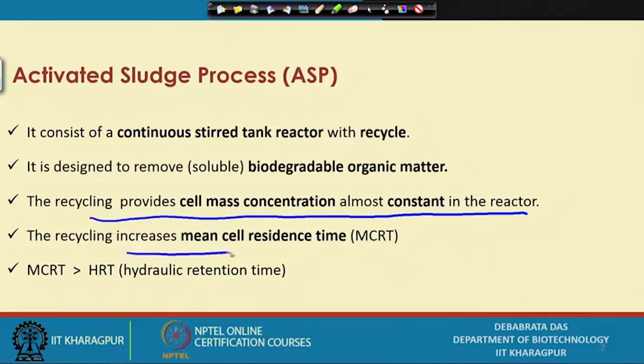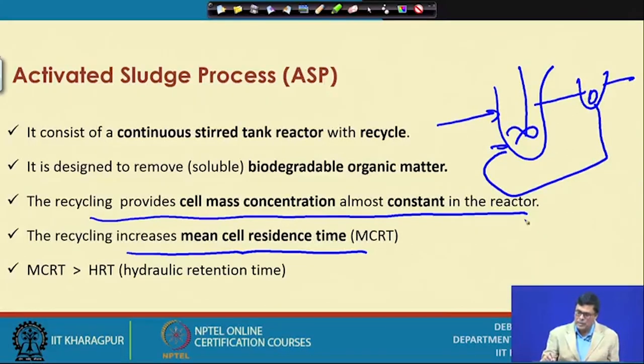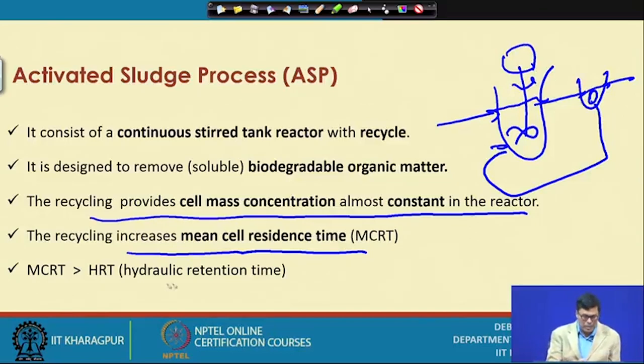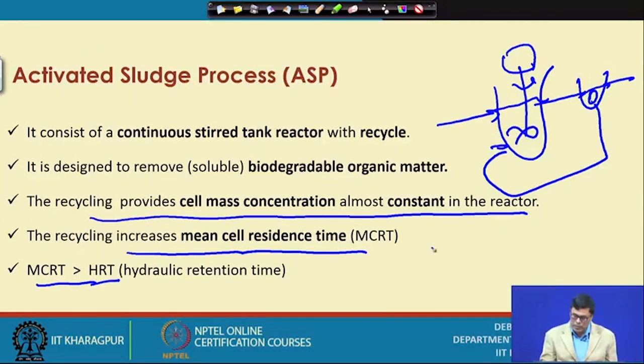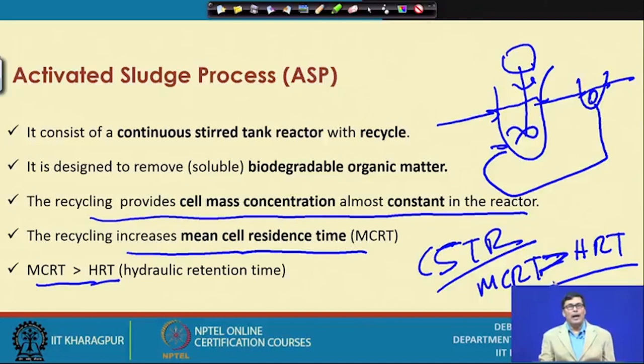Recycling is necessary and it increases the mean cell residence time. Since we are recycling cells back, the cell retention time in the reactor will increase. In that case, the mean cell residence time should be higher than the hydraulic retention time. In case of CSTR or chemostat, the mean cell residence time is equal to the hydraulic retention time. But as soon as you do the recycling, the mean cell residence time is higher than the hydraulic retention time — this is the main purpose of recycling.